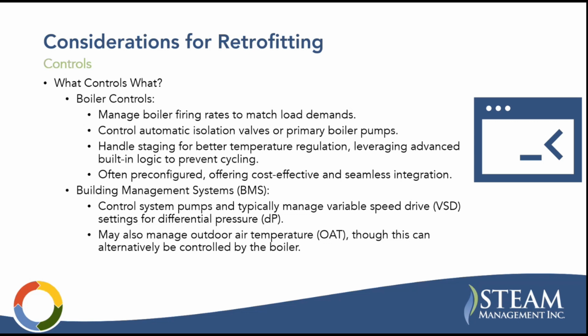But your boiler controls are going to manage your boiler firing rates. They're going to control automatic isolation valves, which is important to make sure that you're maintaining minimum flow through your boilers. And what you want to avoid there is those nuisance trips on high temperature limit, because those usually are associated with a manual reset. So you will not be able to get the boiler back online until you go and actually press that button to manually reset the boiler. So isolation valves are a big part of that.